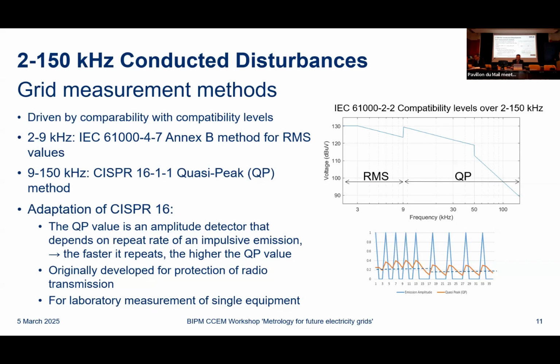Once you go from 9 to 150 kilohertz, the compatibility level is defined in terms of the CISPR 16 quasi-peak value. This comes from the radio frequency standards, and the reason is that there are some existing emission limits, and also a measurement method for individual appliances in the laboratory, where we characterize emissions using the method in CISPR 16. I say we, but it's not necessarily the power quality community, because the quasi-peak was designed to protect radio transmission signals. It is basically a weighting of the rate of repetition of an emission. It looks at the amplitude and at how often it repeats, and the more repetition you have, the higher your quasi-peak, but it will always be lower than your absolute peak. It was designed to characterize the annoyance you get when you're listening to the radio and there's interference.